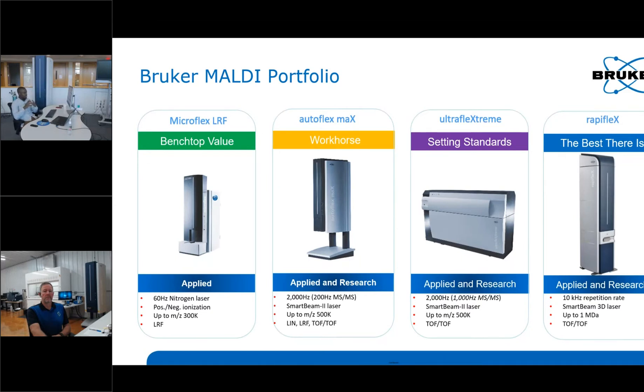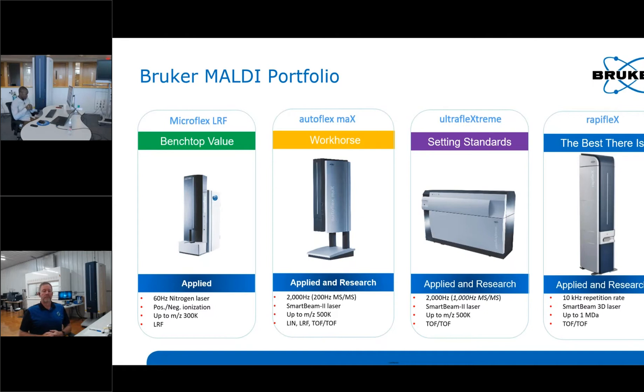MS/MS capabilities are very necessary for structural elucidation as well as confident and specific compound identification, so they add huge value to the instrument. The AutoFlex Max comes equipped with a 2,000 Hz SmartBeam 2 laser — a solid-state laser that lasts a very long time compared to a nitrogen laser — and has a mass range up to 500,000 Dalton.